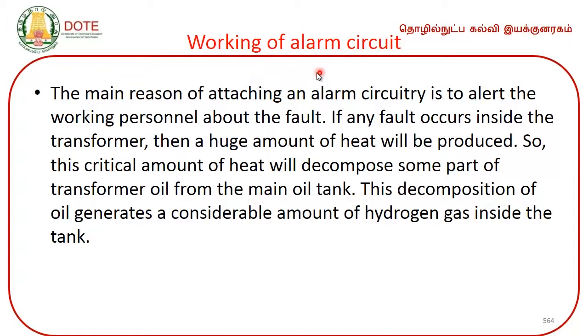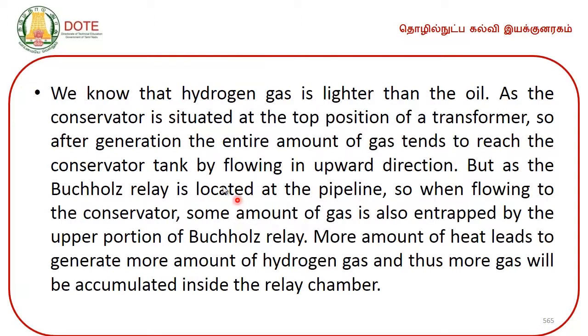Working of alarm circuit. The main reason of attaching an alarm circuitry is to alert the working personnel about the fault. If any fault occurs inside the transformer, then a huge amount of heat will be developed. So, this critical amount of heat will decompose some part of transformer oil from the main oil tank. This decomposition of oil generates a considerable amount of hydrogen gas inside the tank. We know that the hydrogen gas is lighter than the oil. As the conservator is situated at the top position of a transformer, after generation the entire amount of gas tends to reach the conservator tank by flowing in the upward direction.